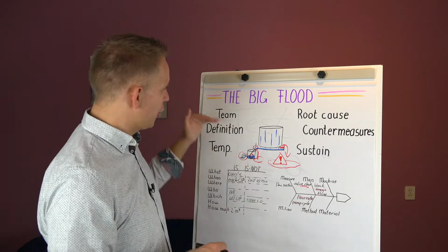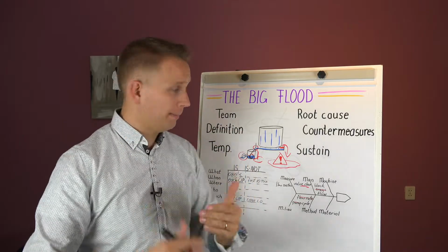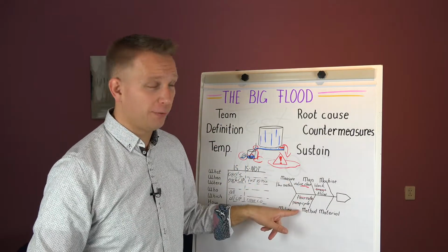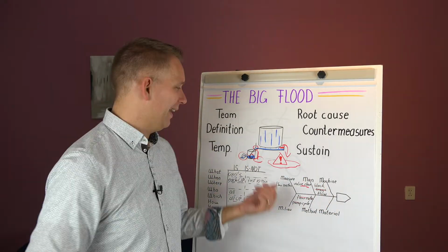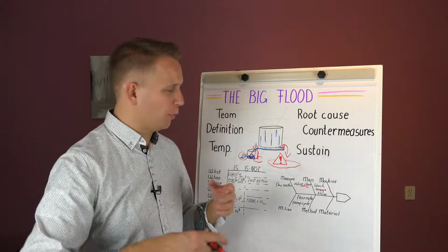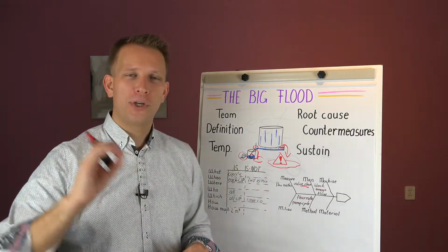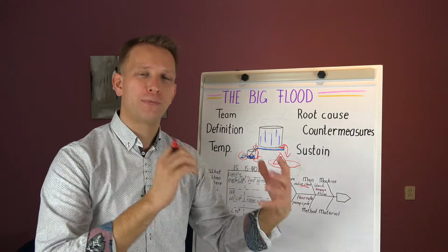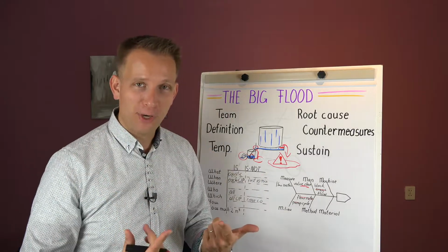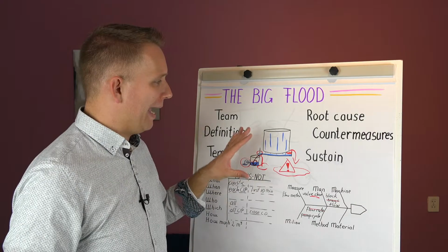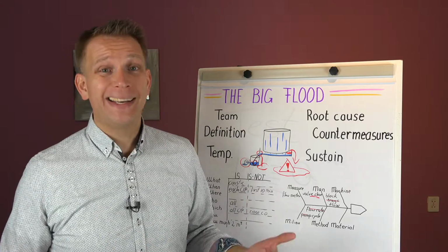And by really going through all of these steps, we managed to find it, and this really frustrated us from time to time as well, because there was sort of a blockage, but not in the pump. We opened up everything. We really checked, the pump was good, the pipes were good. There was sort of a blockage, but it was a flow blockage. It was really because of what the water was doing itself, not any physical blockage of the pipe, but a physics blocking of how the flow was. And once we found that, well, then the countermeasures were quite easy to install.